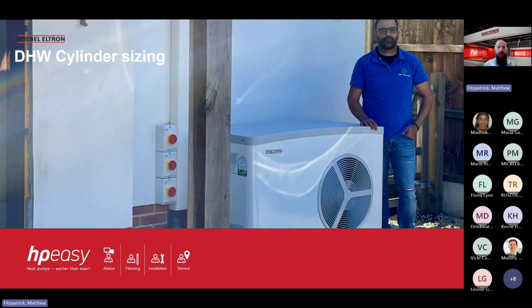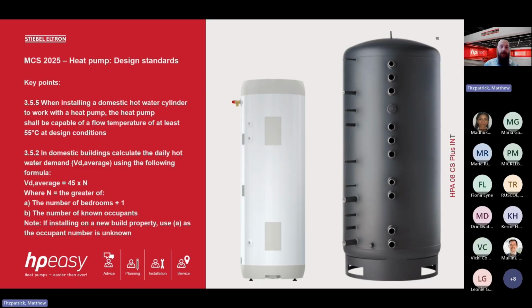So, domestic hot water cylinder sizing. Just a couple of points I've taken from the MCS 2025 heat pump design standards. So one key point is 3.5.5, which is when installing a domestic hot water cylinder to work with the heat pump, it must be capable of at least a 55-degree flow temperature. And that's to be able to bring the domestic hot water cylinder up to 50 degrees. And then when we look at sizing domestic hot water using the MCS 2025 heat pump design standards, on average, it's 45 litres per person. So a simple calculation could be a 3-bedroom property. So let's have a quick look.